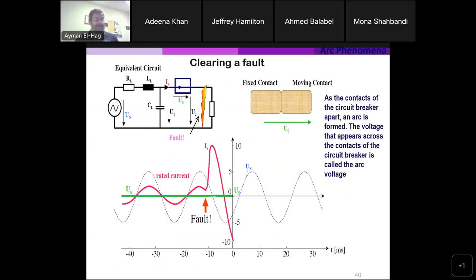Okay, so that is what I'd like to mention about switching the capacitor. High inrush current and higher frequency will lead to higher voltages with higher frequency. The last thing I'd like to talk about is what happens when we clear a fault. So that is a simple system. You have a voltage here. It has a resistance and inductance. This is the capacitance of the system, of the cable, could be, or overhead lines.